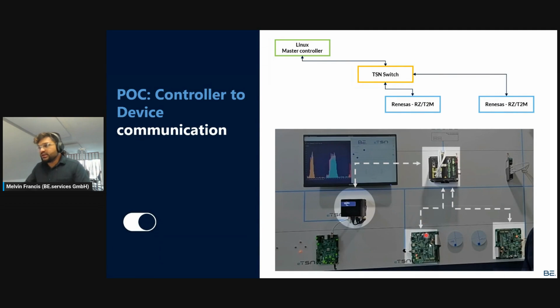Now from this network diagram, you could see that there are totally 1, 2, 3, 4 devices involved, and all these 4 devices are in time synchronization, with a time accuracy of plus or minus 20 nanoseconds, and even sometimes less than that as well. So when we say we could reach microsecond type of synchronization, this gives you the capability to reach a different level of synchronization between the devices and the controllers that you're seeing here.